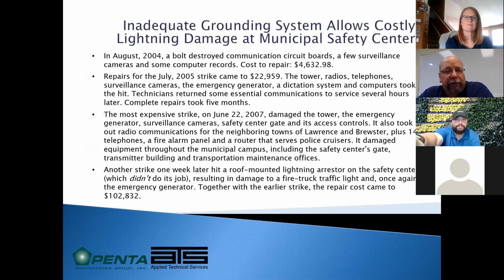The first hit just hit a few communication boards, and it was about $4,600 worth of damage. Then they got hit again the following year in 2005. Tower, radios, telephones, surveillance cameras, emergency generator, and a few other things were hit, and it took almost $23,000. Then in 2007, they were hit twice in 2 weeks, and the total ended up being over $100,000 worth of damage. They finally got to the bottom of what was causing it. It was an issue with the way things were grounded, and they were able to fix that and keep it from happening anymore.